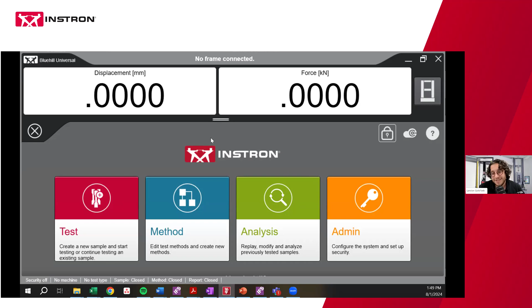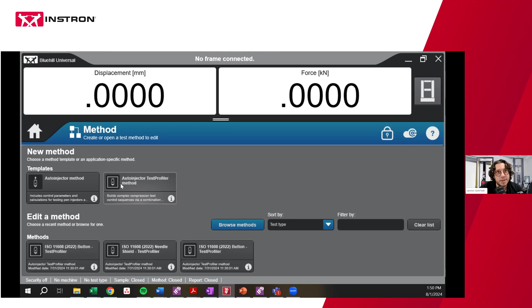Okay, awesome. So we really took a step back and almost built up Bluehill foundationally to work in an auto injector environment. So when you go to choose a method, you'll now see there's only two method types. There's an auto injector method and then a test profiler version of an auto injector method. So you don't see tension and compression because this system is dedicated to auto injector testing. If I click on this method, the first thing you'll notice is the specimen properties are now completely specific to auto injectors.